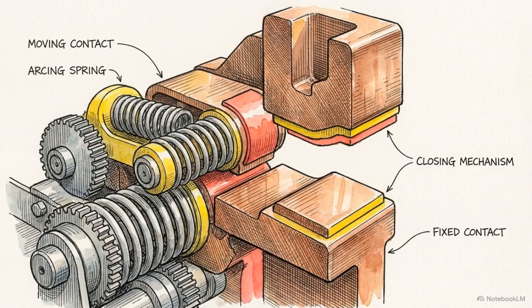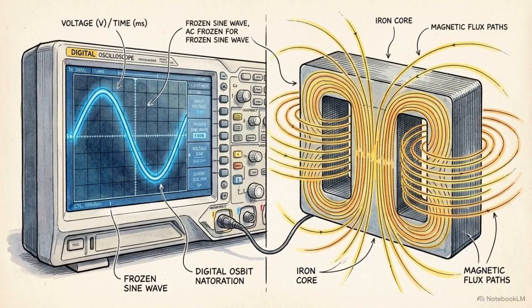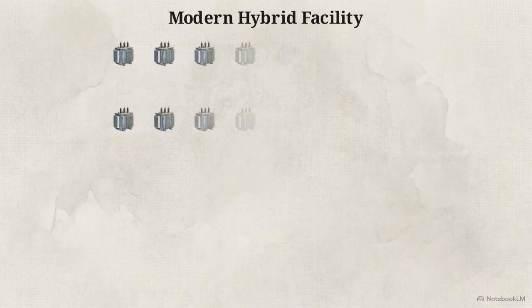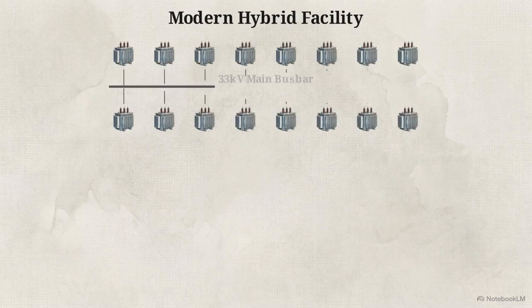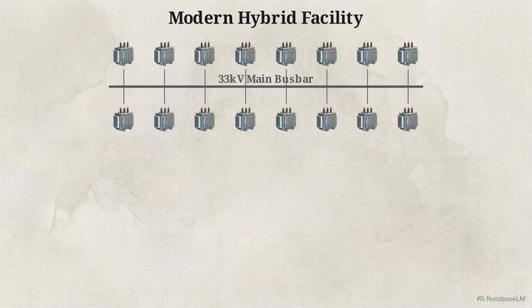The inrush is not a fixed equipment specification. It is a highly variable physical event, dictated entirely by the timing of the breaker and the magnetic history of the core. Now apply that physics to a modern hybrid facility, which might utilize 16 or more medium-sized collector transformers connected to a main busbar.